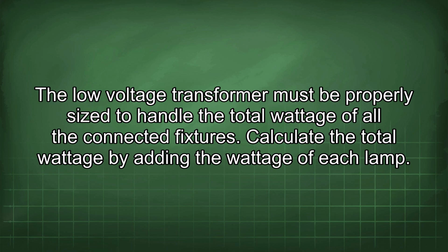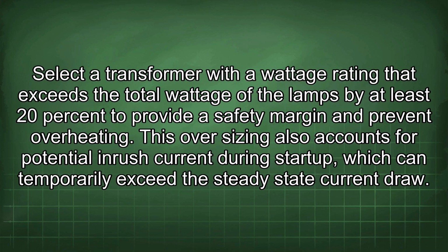The low-voltage transformer must be properly sized to handle the total wattage of all the connected fixtures. Calculate the total wattage by adding the wattage of each lamp. Select a transformer with a wattage rating that exceeds the total wattage of the lamps by at least 20% to provide a safety margin and prevent overheating. This oversizing also accounts for potential inrush current during startup, which can temporarily exceed the steady-state current draw.